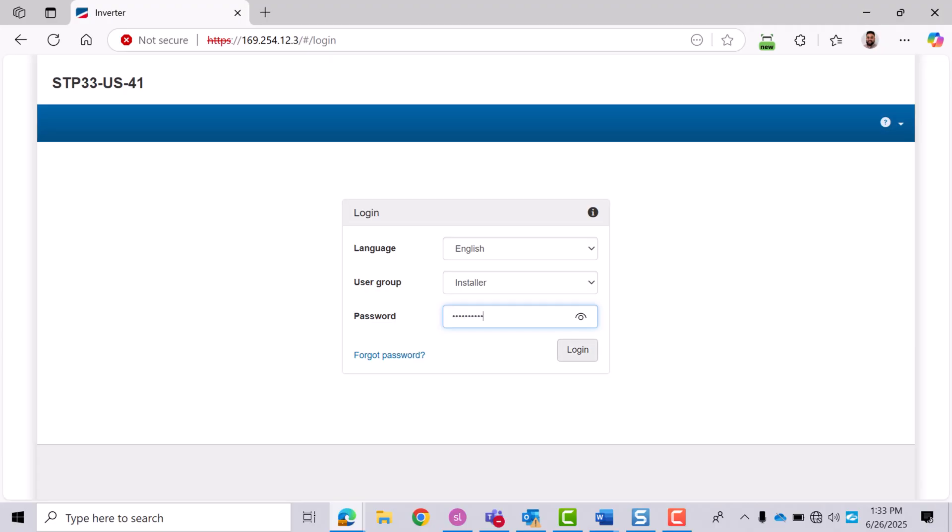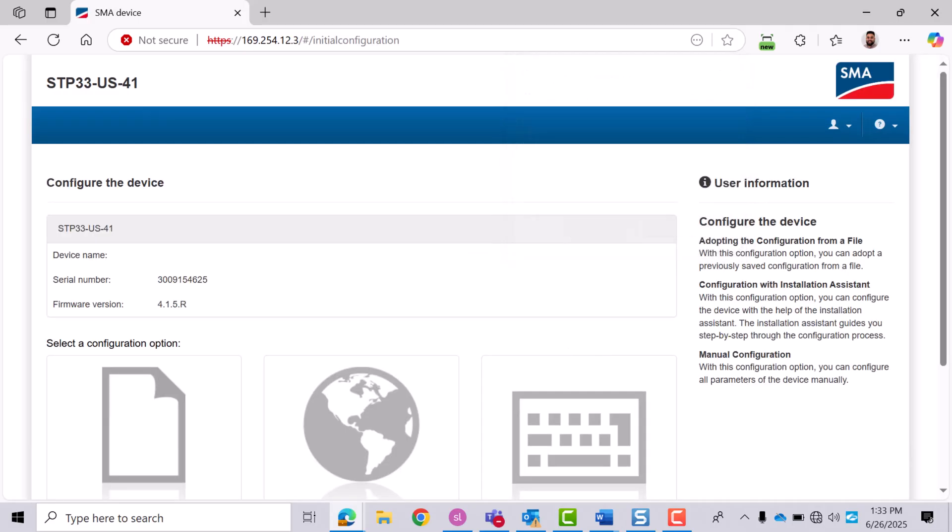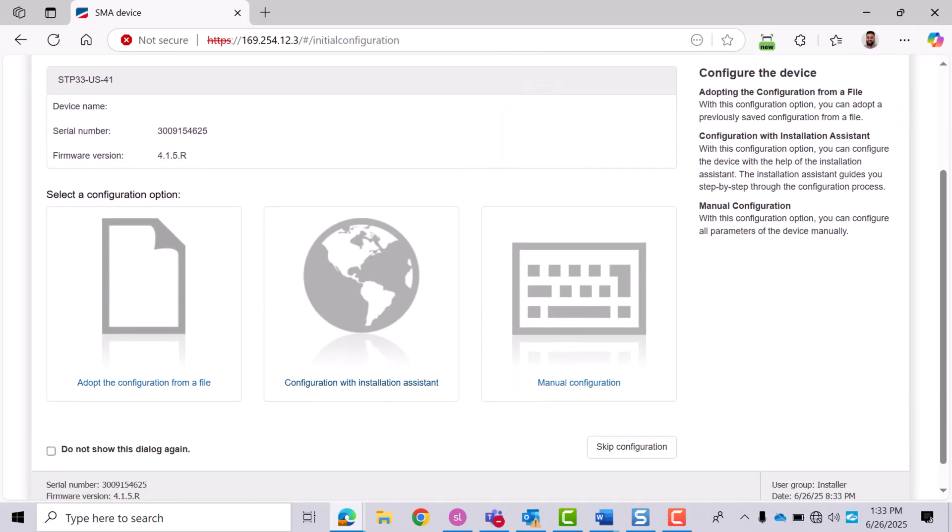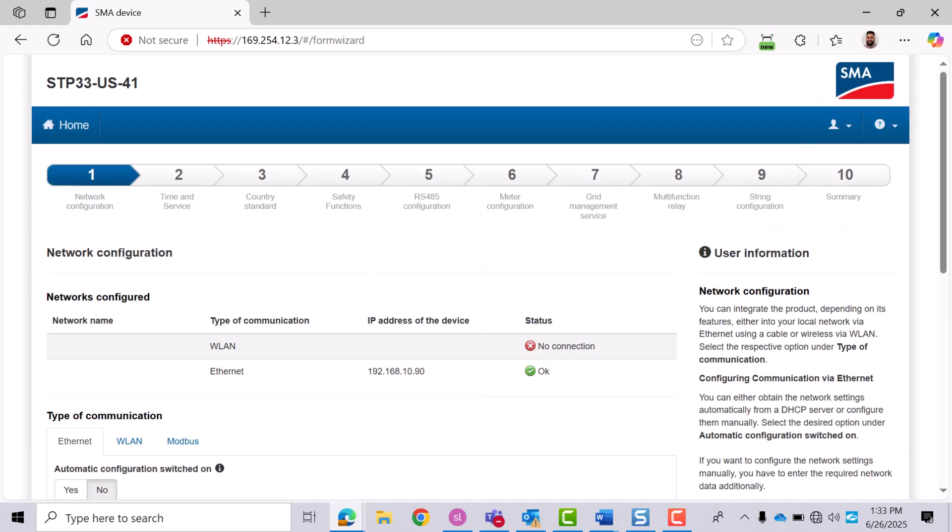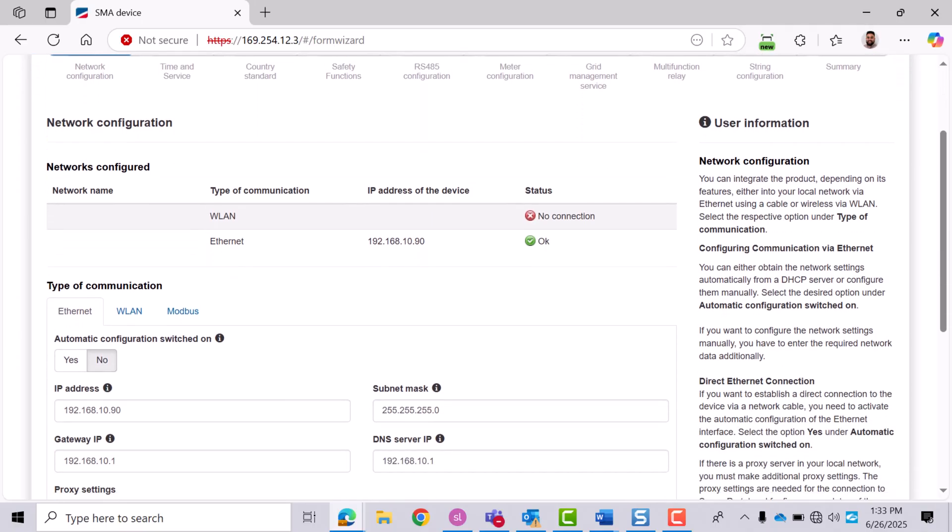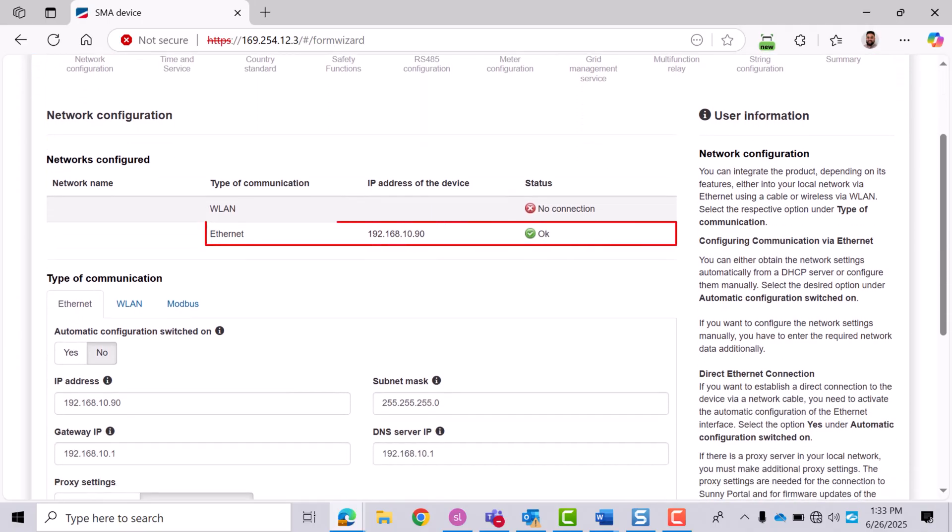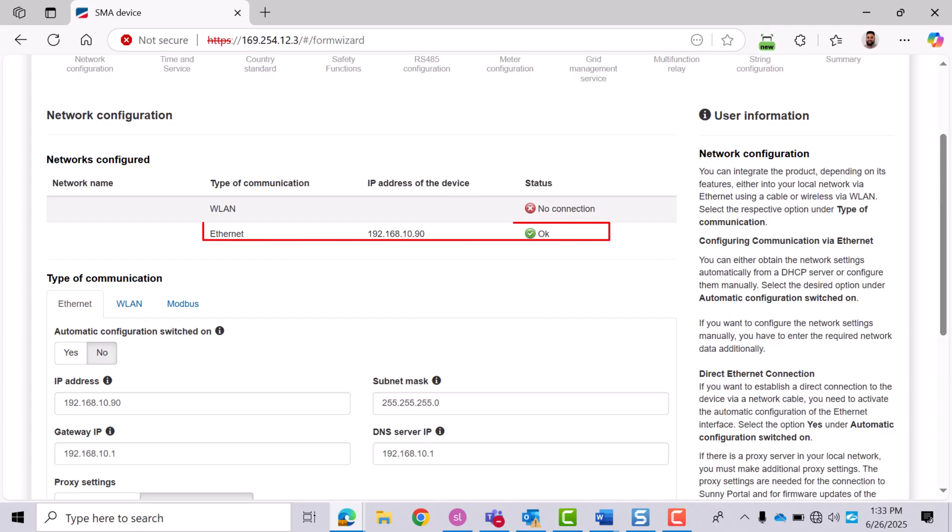Start commissioning by selecting Installation Assistant from the menu. Here you'll configure the inverter's network connection. Please use an Ethernet cord for a more stable and reliable connection. Please note that the Core 1's WiFi functionality is intended solely for commissioning and should not be used for ongoing communication or system control.